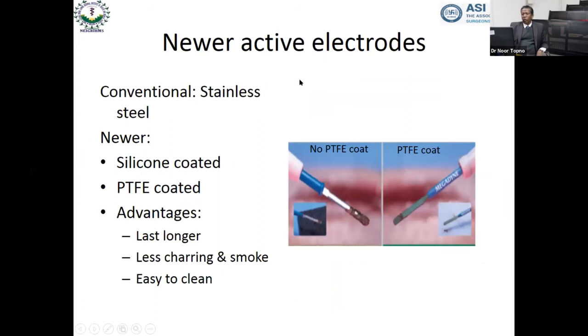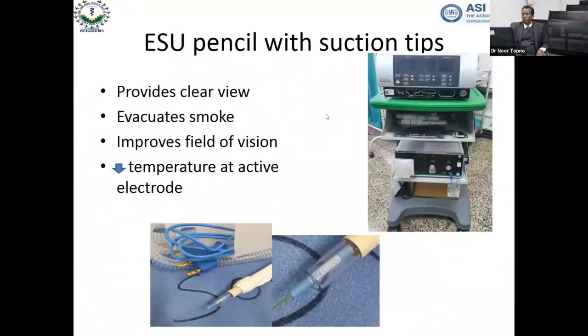Now, again, one of the new things that have happened is vis-a-vis the electrode. This is the kind of charring that happens in the standard stainless steel electrodes that we use. And this is a PTFE coated one, and the charring effect is much less and it's much easier to clean. That apart, of course, you have silicone coated also, and also ceramic electrodes.